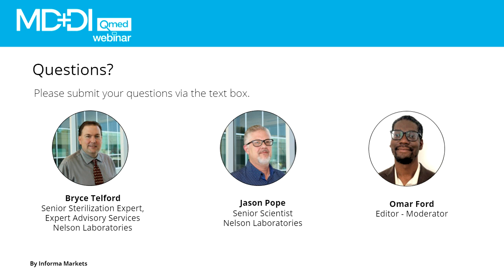So I'm just going to read the question again. In addition to sterilization of reusable devices at healthcare facility, is there serious potential of H2O2 sterilization for single-use devices by the manufacturer? We did touch on this, and yes, I would say there is serious potential of vaporized hydrogen peroxide sterilization for single-use devices by the manufacturer. This is a sterilization modality that might be a great fit for, say, end-of-the-line sterilization, where it comes off the line and it goes into a vaporized hydrogen peroxide sterilizer, is sterilized, and then loaded into final packaging, final secondary packaging.